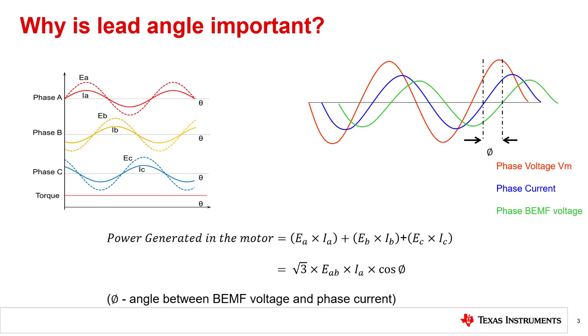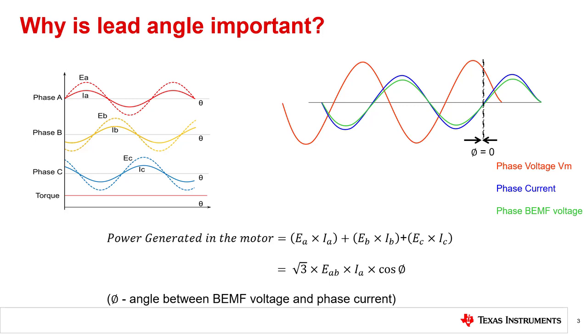The generated power and torque will be maximum when the phase current and back EMF are aligned. When phase current and back EMF are aligned, angle phi is zero. When phi is zero, maximum power is generated in the motor as cosine of phi is one. To achieve maximum efficiency, lead angle should be adjusted such that the angle between back EMF voltage and phase current is zero.